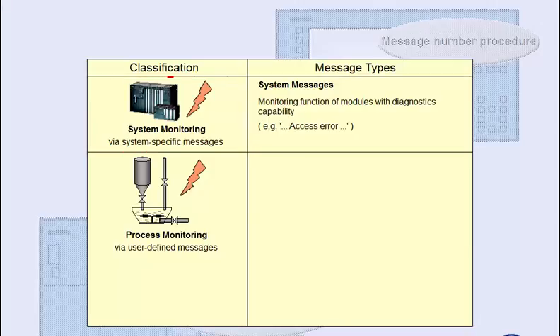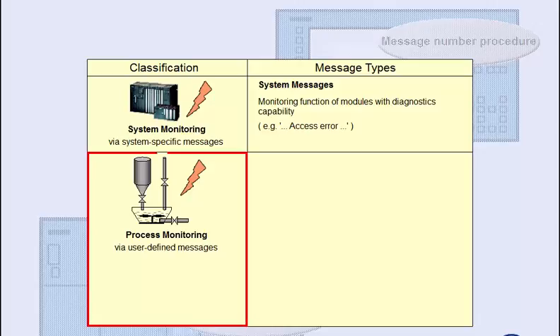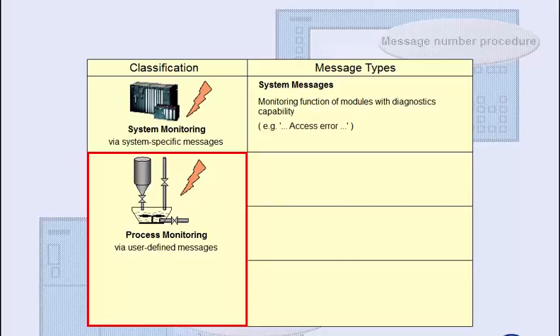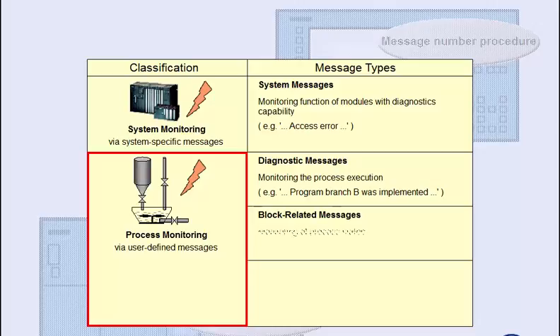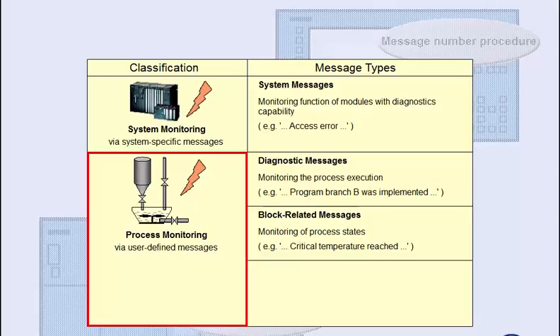With user-defined messages, on the other hand, the project planner determines the event that will trigger a message, and the message text. Three types of user-defined messages can be distinguished. Diagnostic messages are best suited for monitoring the process execution. Block-related messages indicate process states. They can contain accompanying values that were recorded at the time of the event. The message text may vary depending on the accompanying values.